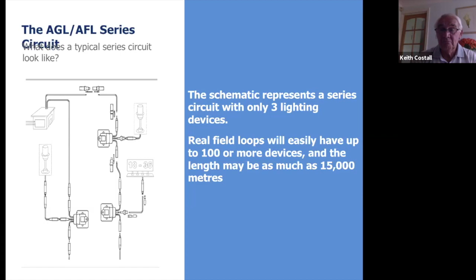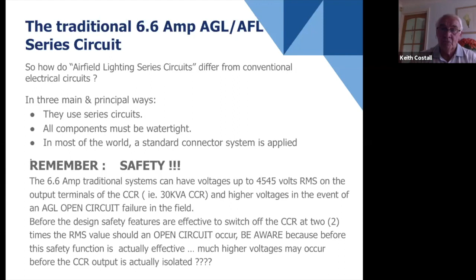So remember, safety. If you are going to have leakage from a connector, then you're going to have an electrical earth. And if you get multiple electrical earths in a field, that is two or more, then you are going to have an operational effect on your lighting system. Some of the lights will go dim or go out or flicker on and off. And at the same time, we still have a live electrical circuit. Of course, this design of the system, the standard system, means that a CCR will stay operating wherever possible. So earths in the field do not switch off the CCR, which makes it dangerous.